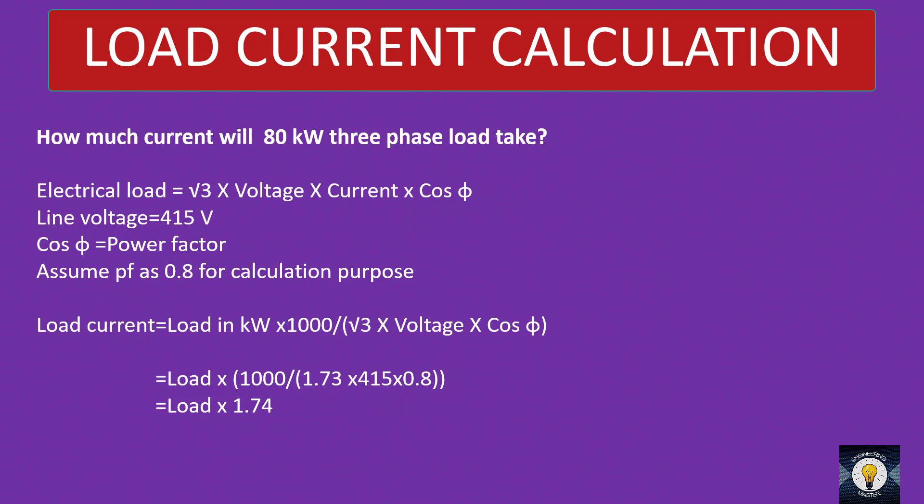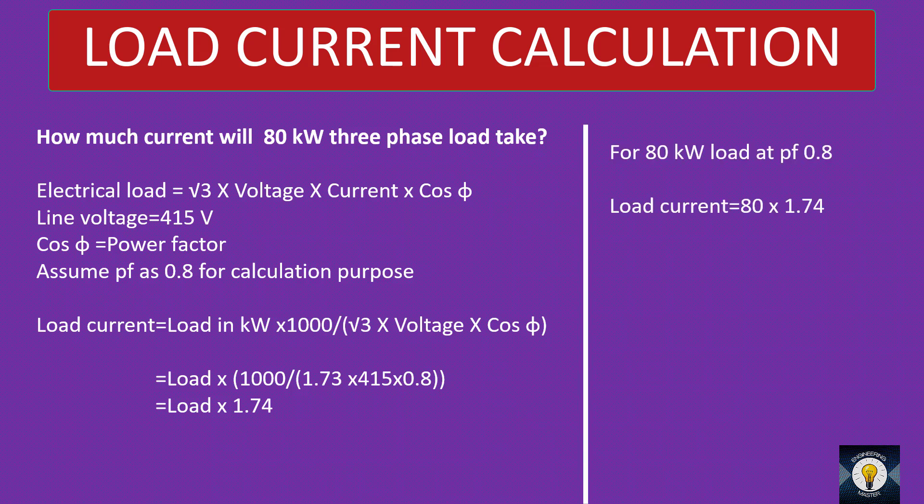If someone asks what is the current drawn by a 10 kW three-phase load, just multiply the load by 1.74 — that is 10 into 1.74, approximately 17.4 A. Now addressing our main question: for an 80 kW load at 0.8 power factor, load current equals 80 into 1.74, which gives 139.2 ampere. If your line voltage is 415 V, remember 1.74 for power factor 0.8 and just multiply the load in kW by 1.74 to get the load current.